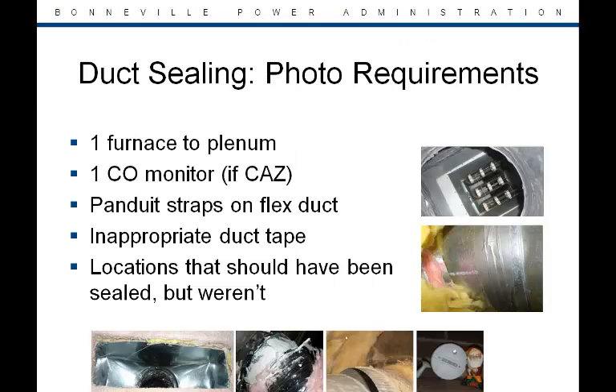When inspecting a duct sealing job, QA inspectors must take a clear photo of the furnace to plenum connection, the CO monitor, if there is a combustion appliance zone, the Panduit straps on flex duct, any inappropriate duct tape, and any locations that should have been sealed but weren't.